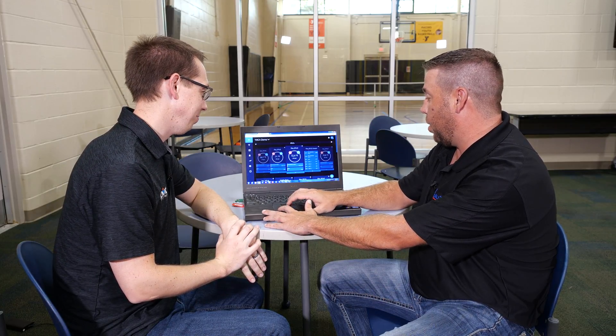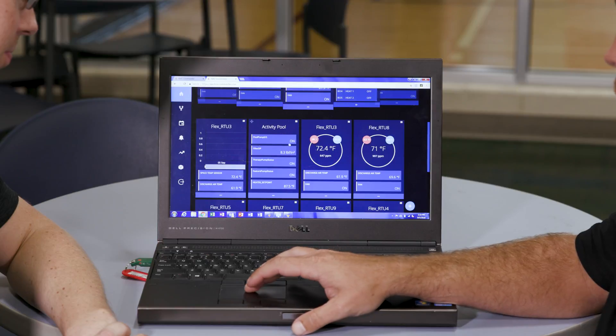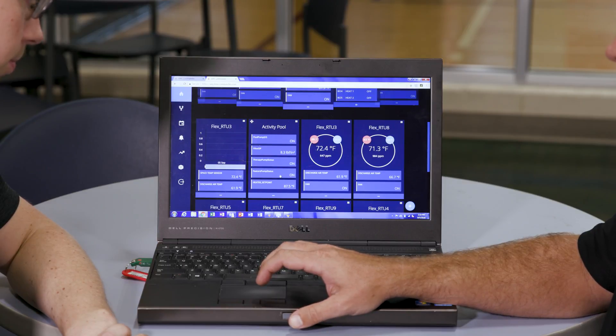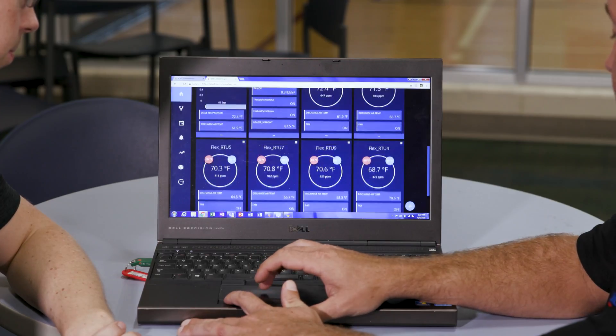The KMC Commander platform is excellent for HVAC solutions. While you guys were setting that up, I was walking around the building and I saw a couple of areas I thought we could plug into this — something like electric metering or the pool. Funny you say that, Tim — we actually did. We have a couple other cards in here that we created. We actually have an activity pool on site. For this pool, we have pool start/stop, we have a filter DP to tell them when they need to back flush, a couple of secondary pumps to tell them when they're running, and also the heater set point — how hot they want their pool. It's writable; they can change it right here off the KPI. And for electric metering, we are also looking at real power currently. Operational efficiencies, energy efficiencies — all that can now be tracked both here on-site, but also remotely via a phone, tablet, or laptop.